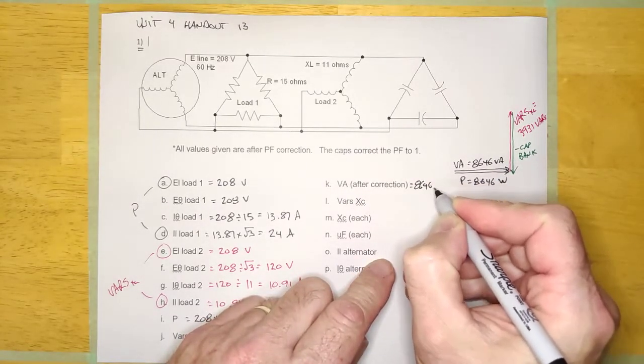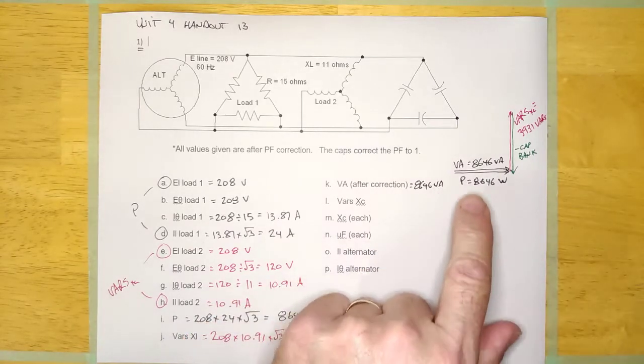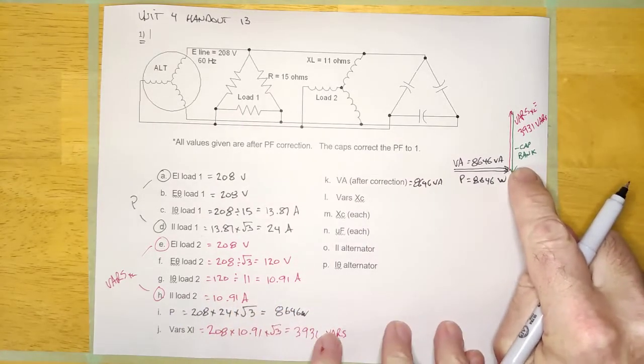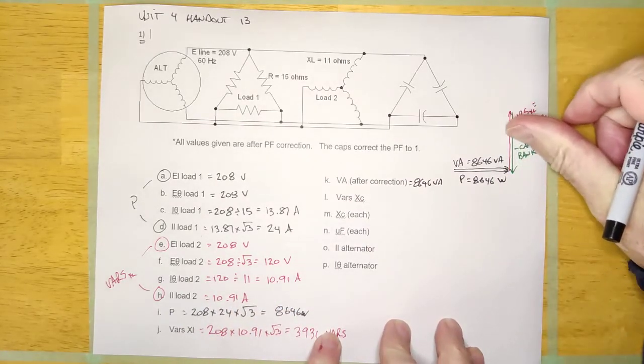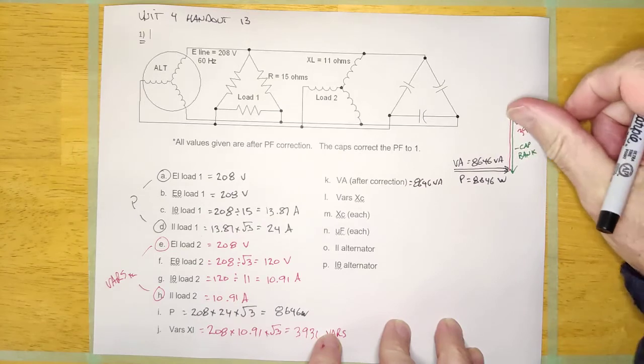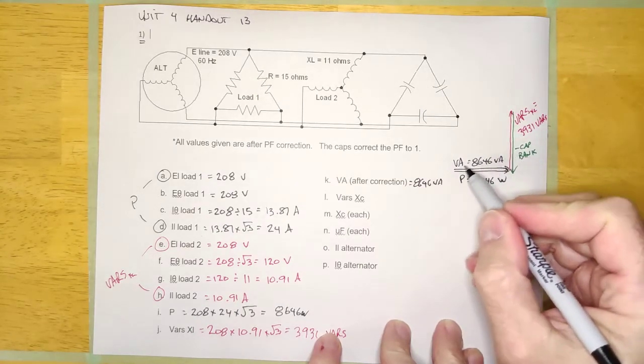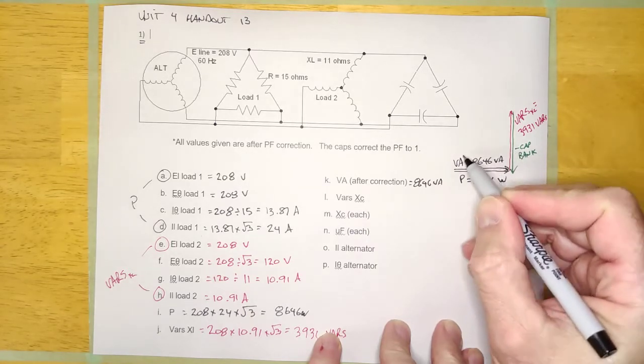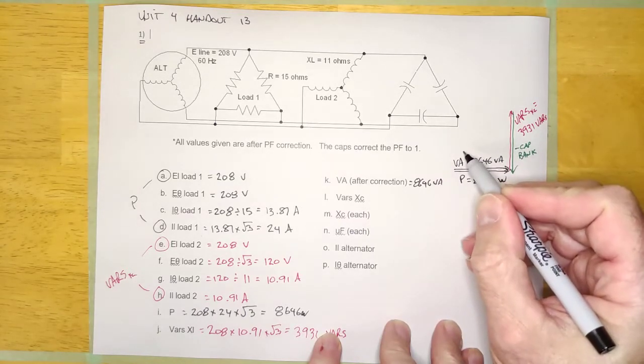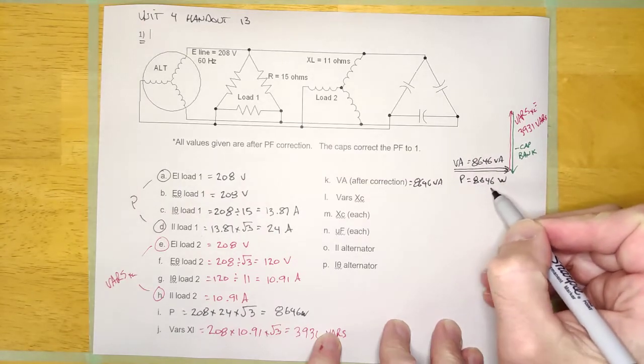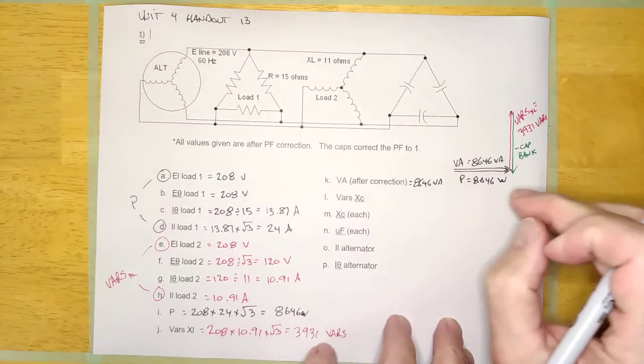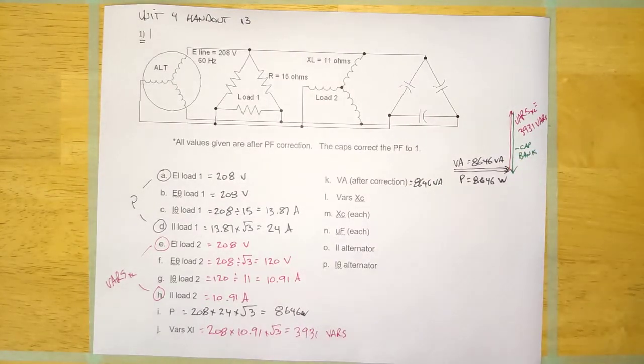If I was correcting to 90%, I'd have my 8,646 watts, my vars XL, and my vars XC coming down part of the way from the capacitor bank. Then I'd have my power factor of 0.9 and I could calculate the VA by dividing the watts by 0.9. So correcting to 0.9 works the same way, just looks a little different.